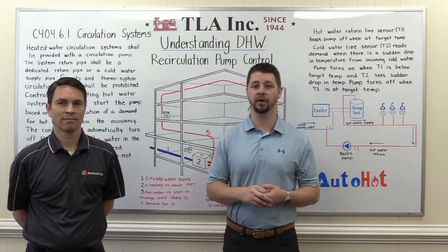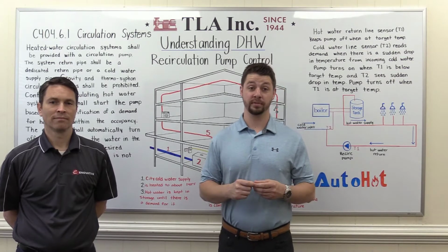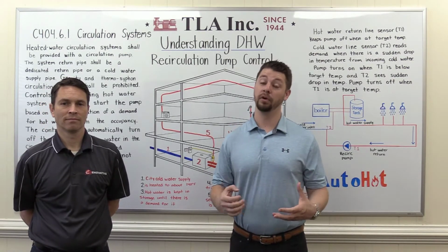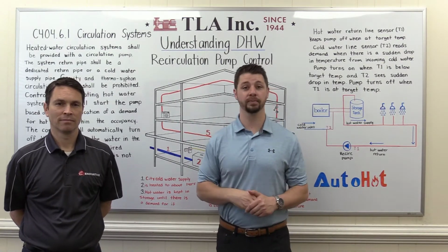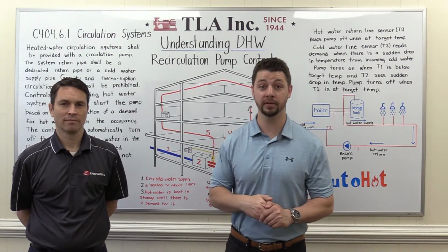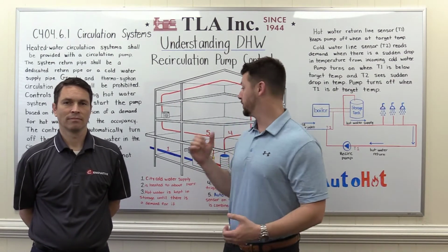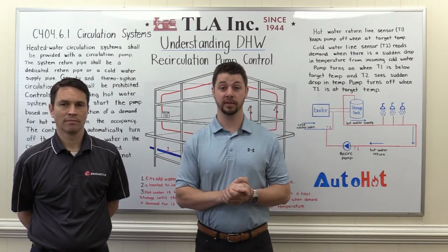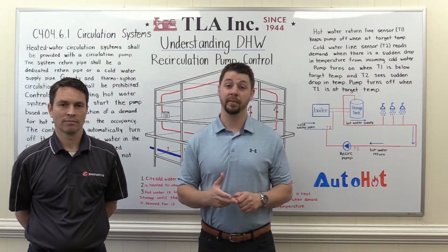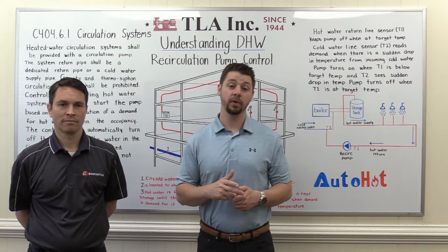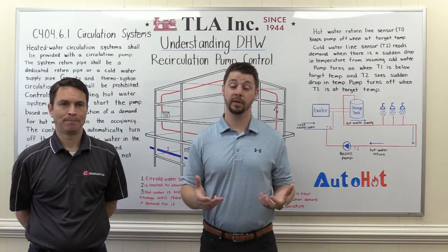Today we're going to focus on domestic hot water recirculation control systems, specifically as it relates to demand control on the pumps. I don't know how many of you engineers are aware of the new code requirements, but if you haven't browsed through them in the past few years, you're probably missing a lot of big changes as it comes to control of recirculation pumps on recirc systems. There's a lot of compliancy things, there's a lot of confusion on what that demand control looks like, and no longer can we get away with aquastats and timers and things like that. So it's something to be aware of.